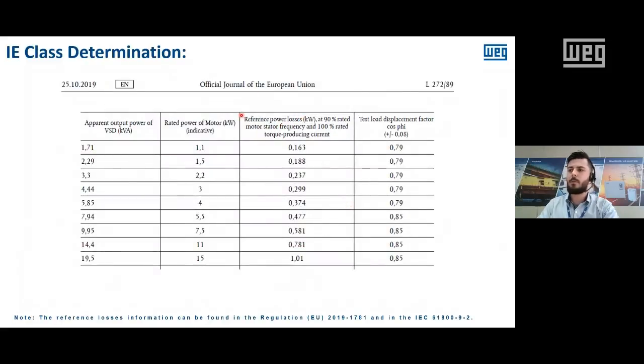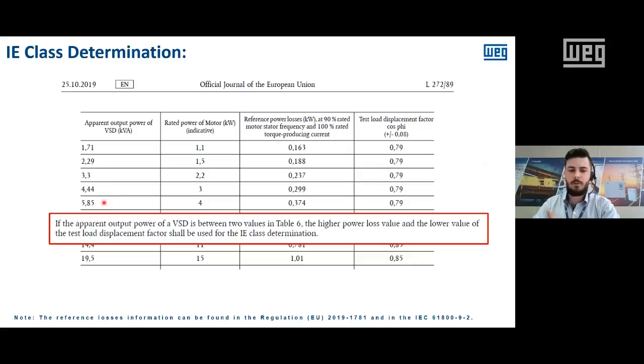This is the table of the regulation where you have the reference losses of the complete drive modules. And then let's get the reference value so we can compare with the one that we have in our drive. One important point to mention: the regulation states that if the apparent output power of a variable speed drive is between two values of this table, you should take the higher power losses. Which means here we have the case of a 3.33 kVA drive. It's a little bit above this one here, so we should take the reference losses of this one, which is the 4.44 kVA. And then we are going to this value. So if we make the calculation, the reference IE CDM losses is going to be 299 watts.